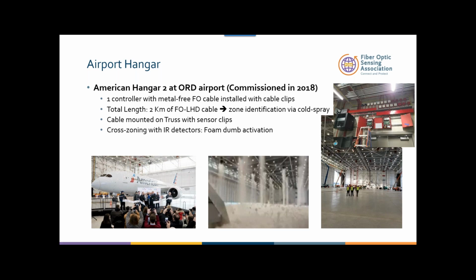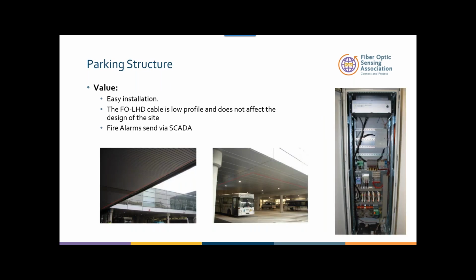Every time a hangar gets installed or set up, that means the airport is growing. At the same time, we are monitoring these new assets, which are planes. 737 is the example in this case. The mayor of Chicago is there, and you can see in this application that the foam and the sprinkling system have to be activated with our linear detection and the IR cameras and IR sensors. Foam is very, very expensive, so you can literally pinpoint where the fire is happening, and then you can actually flood the system.